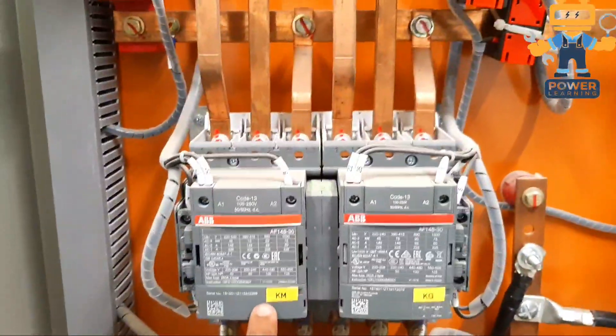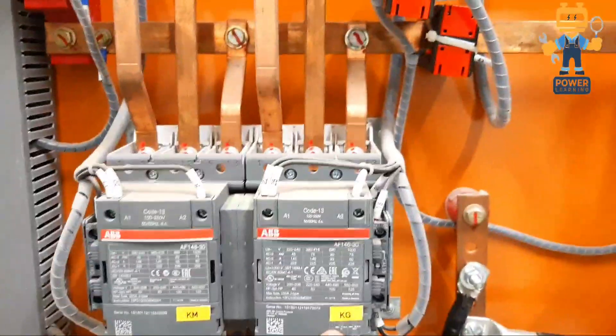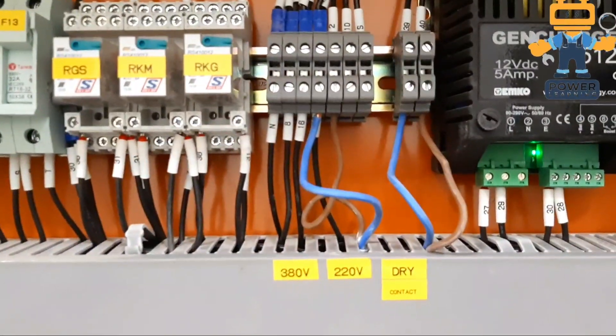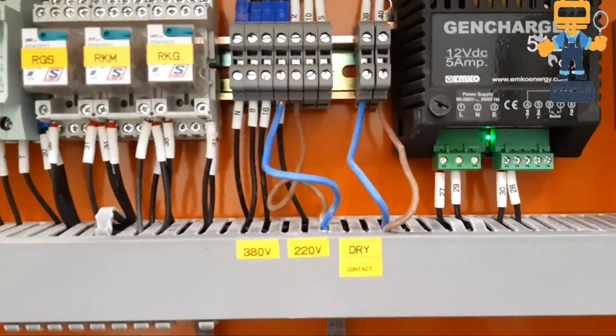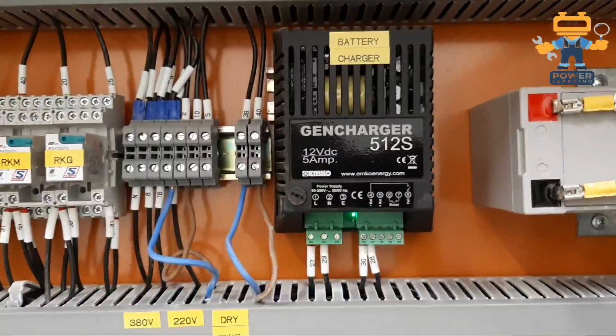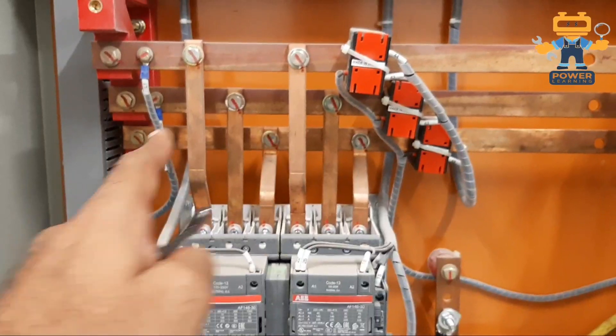RGS is remote generator start, RKM is relay for mains contactor, and RKG is relay for generator contactor. These are our connections. This one is 220 volt and other is dry contact for remote start. This is remote start. Here we have our battery charger and this is our battery.